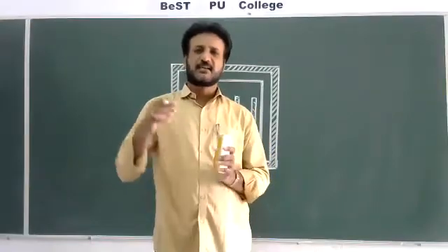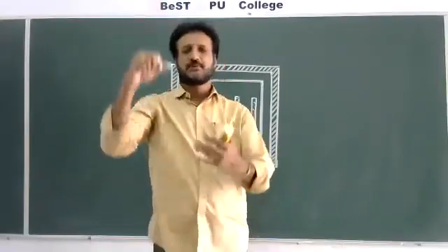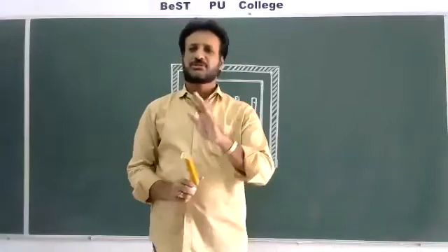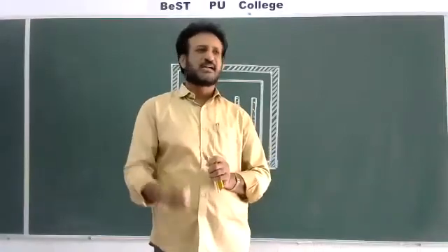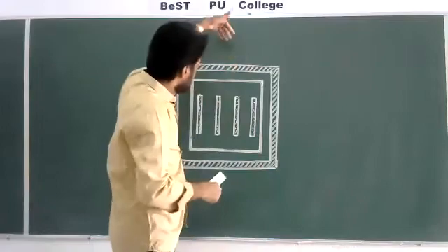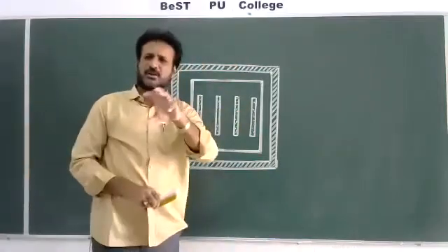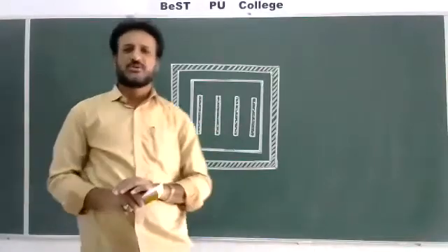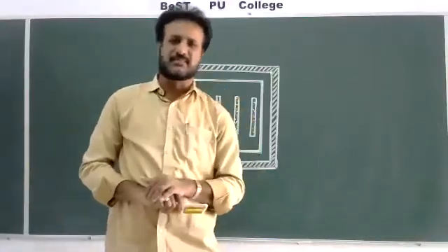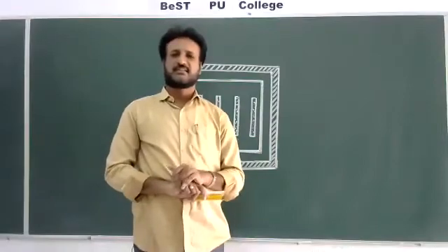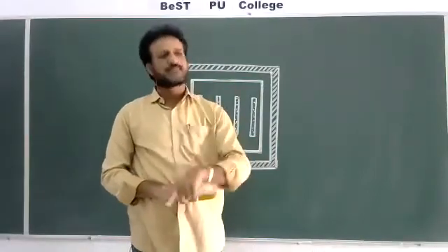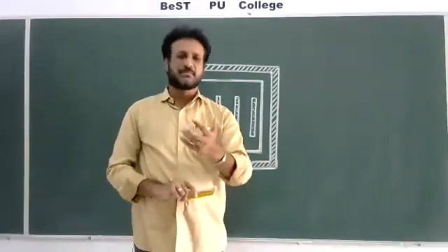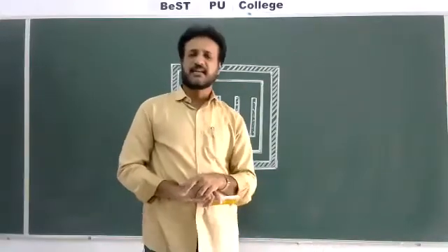Whenever the rods are pulled outside, the reaction will go on automatically. Whenever we want to stop the reaction, we switch the remote and all the control rods go inside the reactor and capture all the neutrons so that the reaction is stopped. That's why they should have good absorbing property of neutrons, and they should not slow down the neutrons. They have to absorb the neutrons. That's why you should take cadmium or boron as control rods.